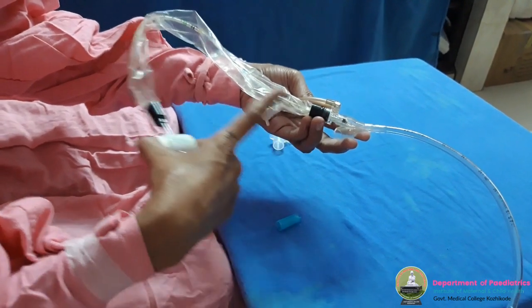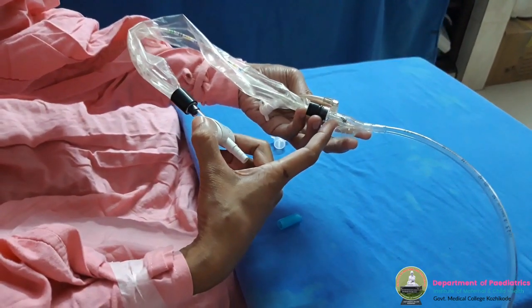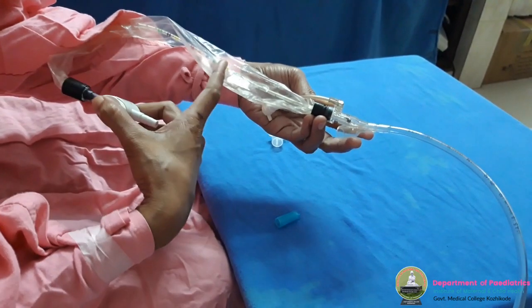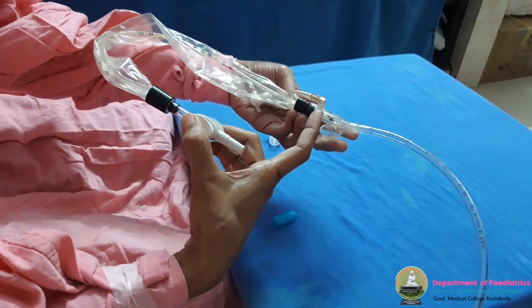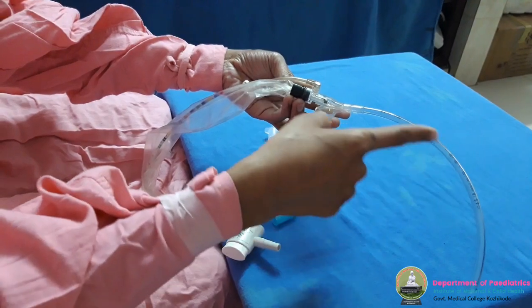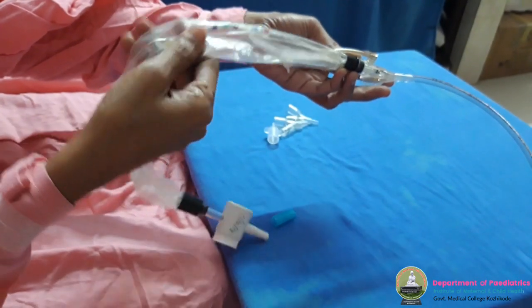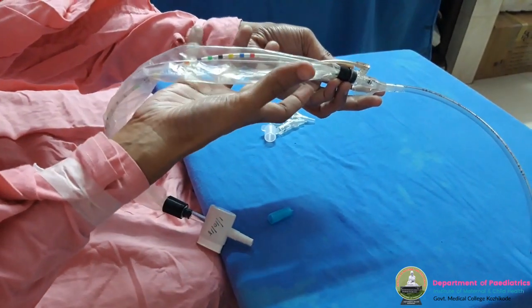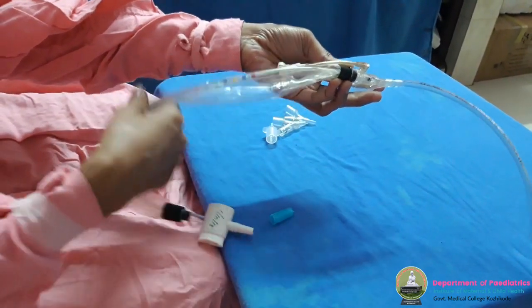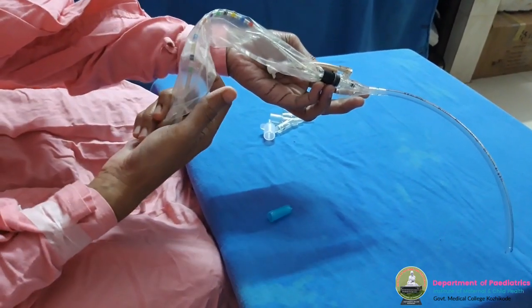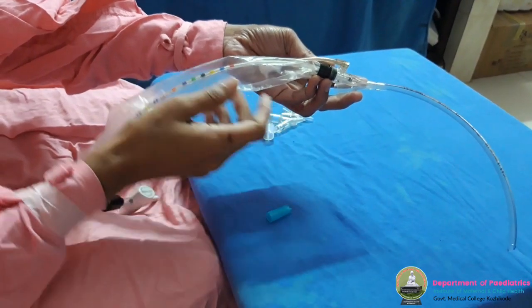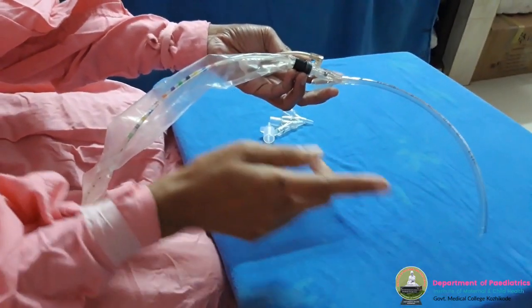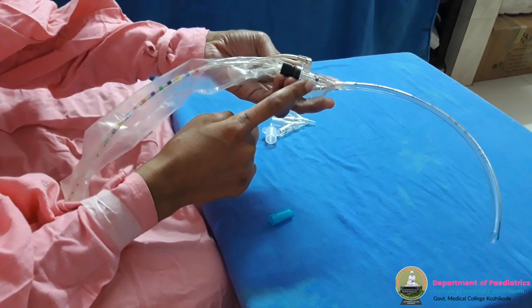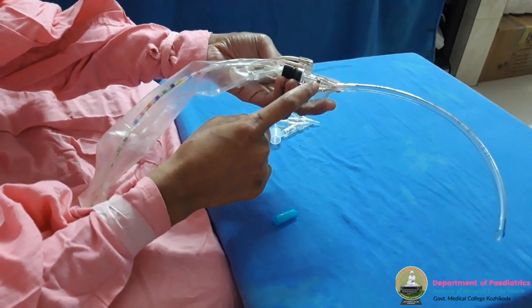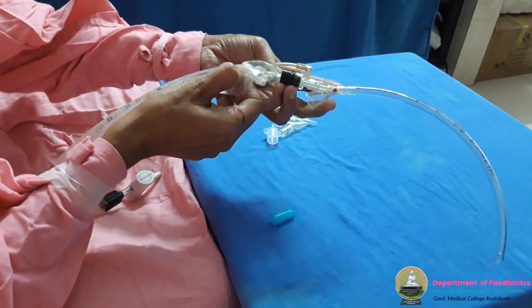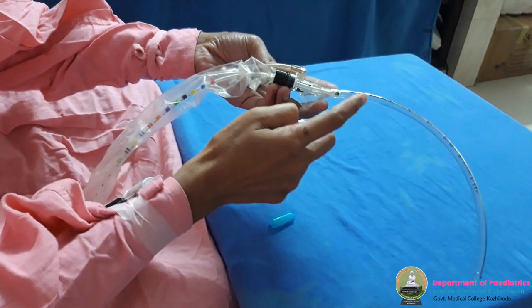You should not pull it further, because this catheter will enter this polythene cover, and this area will cause leakage of gas from the ventilator circuit into this polythene cover, and this polythene cover will inflate like a balloon. Then this device has to be replaced with a new one. You cannot ventilate a patient once there is a leak from the system. So this is a very important point. It should be in the chamber only. It should not be in the circuit or in the ET tube.